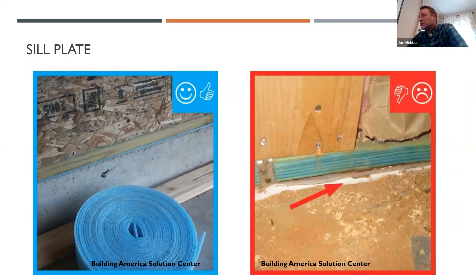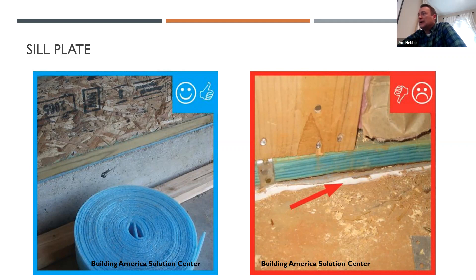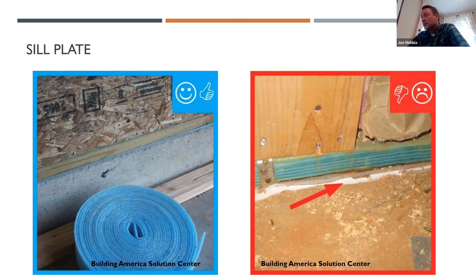The sill plate joint with the foundation must be sealed. This is an area where we see a lot of blower door tests failing. On the left you see a product doing air sealing between the sill plate and the foundation; on the right, there's been no sealing done. This can be especially problematic because we've got a straight piece of lumber sitting on top of a foundation that may have bumps and curves, so there are a lot of places for air to get in. There are gaskets, foams, and caulks — any of these are allowed, but you have to do something at that joint. You really probably won't pass your blower door test if you don't.